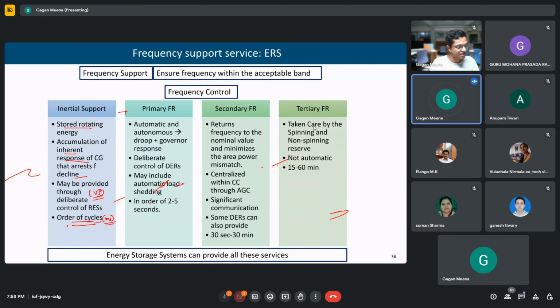It may not be the same, it may be the same, it depends, but it will result in one value. All the generators will operate at one frequency. Droop characteristics we have seen last week. It may include automatic load shedding. So it is fully automatic, and this happens in the order of seconds, 2 to 5 seconds. Now these two are not automatic. So these first two do not require any kind of communication. They will operate on their own. At the secondary and tertiary levels, they require communication.